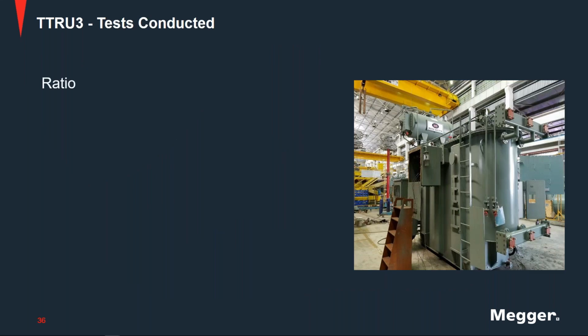Some of the tests that are conducted with the Ttru3: while it is a true three-phase device, we can test single-phase switched if needed. If you want to try and match results to your historical results, that is why we have it. And then also, not every transformer is going to operate 100% correct all the time. If you have a damaged winding, then you need to be able to excite one phase at a time to determine if the other two windings are still functioning or to try and isolate that problem winding.